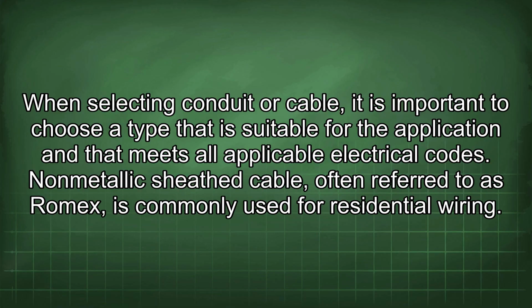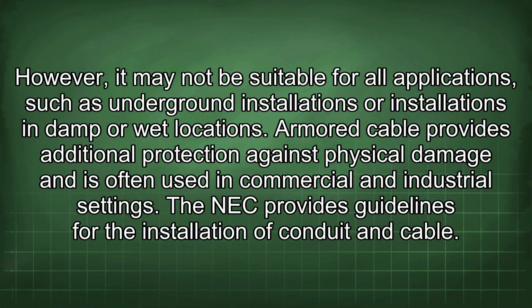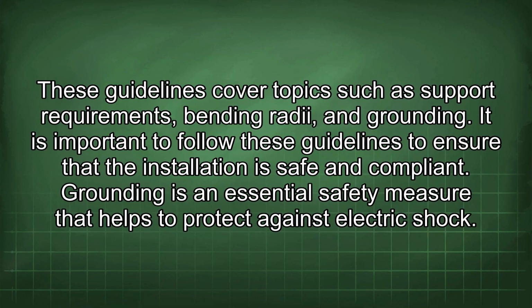Non-metallic sheath cable, often referred to as Romex, is commonly used for residential wiring. However, it may not be suitable for all applications, such as underground installations or installations in damp or wet locations. Armored cable provides additional protection against physical damage and is often used in commercial and industrial settings. The NEC provides guidelines for the installation of conduit and cable. These guidelines cover topics such as support requirements, bending radii, and grounding. It is important to follow these guidelines to ensure that the installation is safe and compliant.